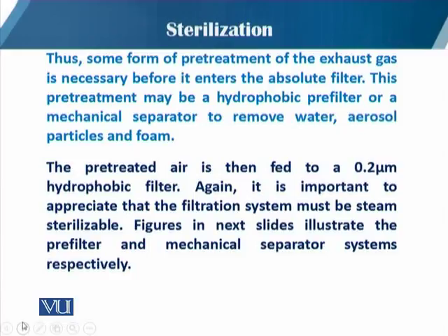So we have to use some pre-filters or some treatment just to remove the water, or some condensation process in which most of the water molecules become condensed and remain inside the fermentation vessel. This pre-treatment may be hydrophobic pre-filters or a mechanical separator to remove the water, aerosol particles and the foam.